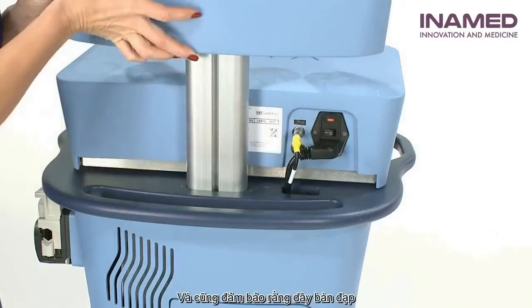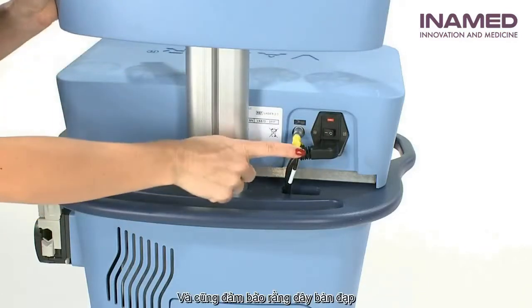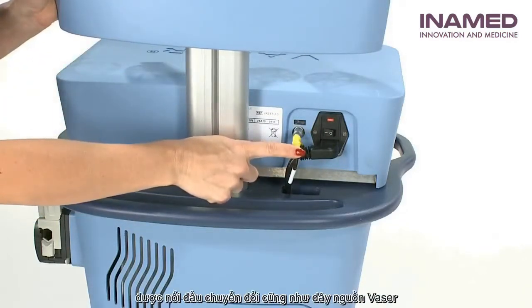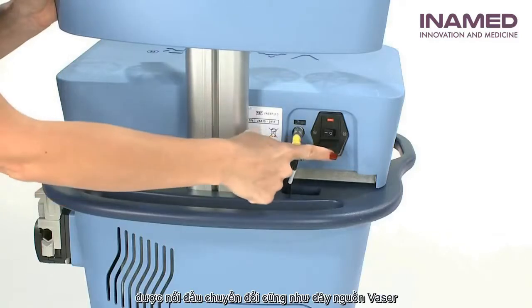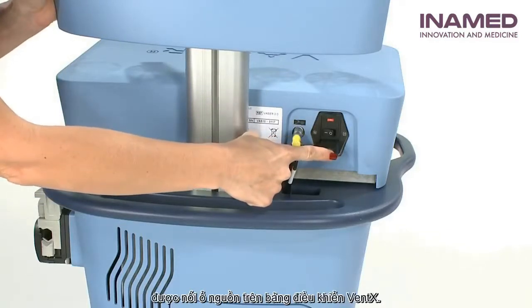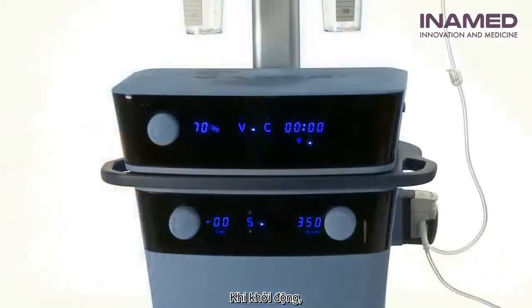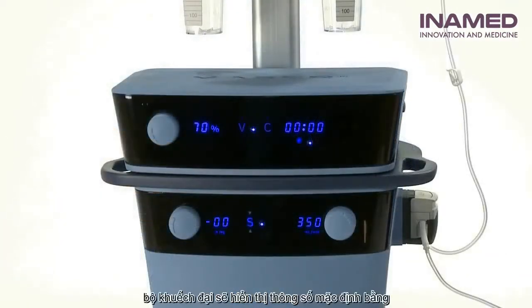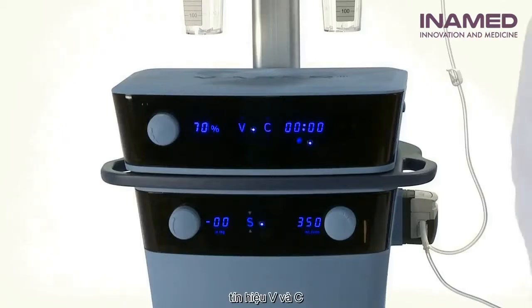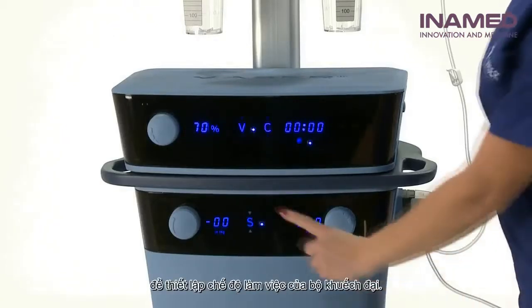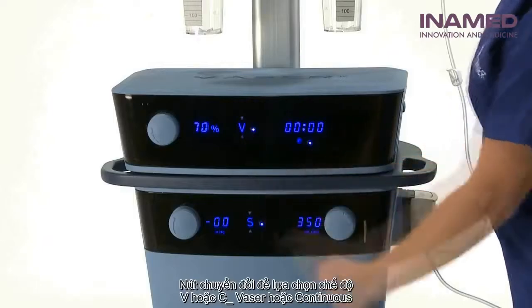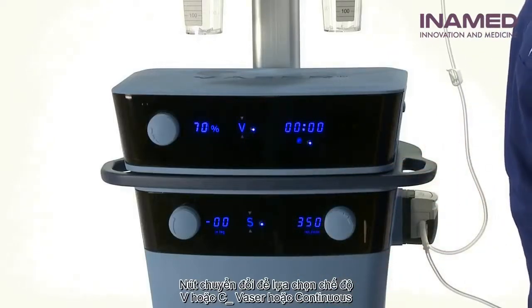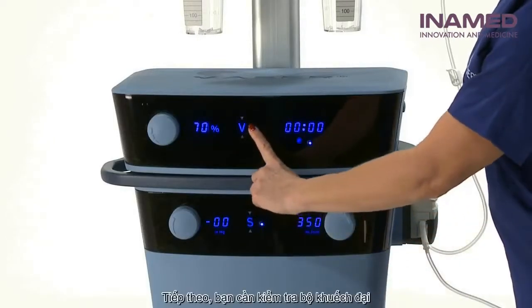the power switch on. Also, ensure the Vaser foot switch cord is connected to the Vaser foot switch receptacle, as well as the Vaser power cord connected to its respective power module on the VentX console. Upon initial power on, the Vaser amplifier should always default to a standby operating mode indicated by a flashing V and C. To place the amplifier into a working mode, toggle the mode switch to select either V or C, Vaser or continuous mode, respectively.